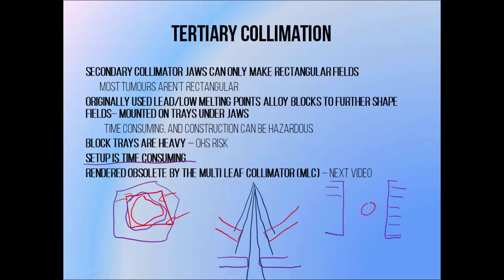Briefly, multi-leaf collimators are a set of collimator jaws that have been divided into small sections or leaves which can move independently. They allow us to produce electronically programmed beam shapes without staff having to change them manually.